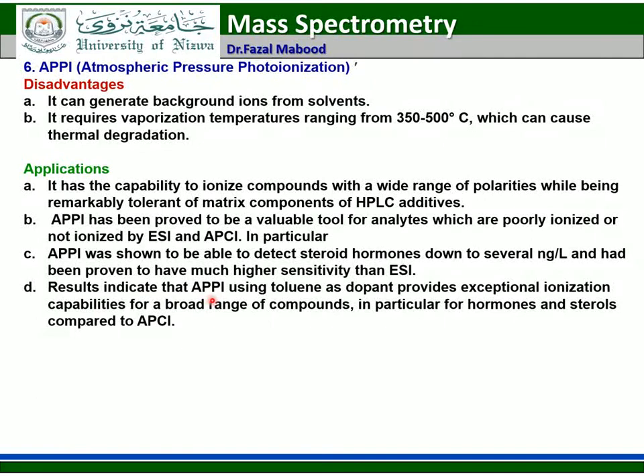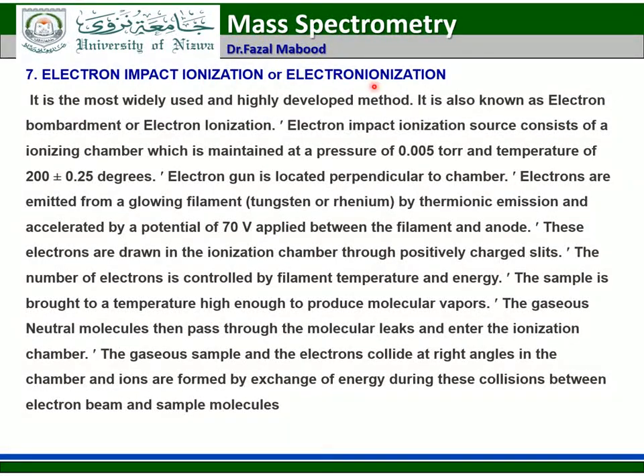Electron impact ionization (EI), also known as electron bombardment or electron ionization, is the most widely used and highly developed method. The EI ionization source consists of an ionization chamber maintained at a pressure of 0.005 torr and a temperature of 200 degrees Celsius. An electron gun is located perpendicular to the chamber; electrons are emitted by thermionic emission and accelerated by a potential of 70 volts applied between the filament and the anode. These electrons are drawn into the ionization chamber through a positively charged slit. The number of electrons is controlled by filament temperature and energy. The sample is brought to a temperature high enough to produce molecular vapors, which then pass through molecular leaks and enter the ionization chamber where gaseous sample molecules and electrons collide at right angles, forming ions by energy exchange.